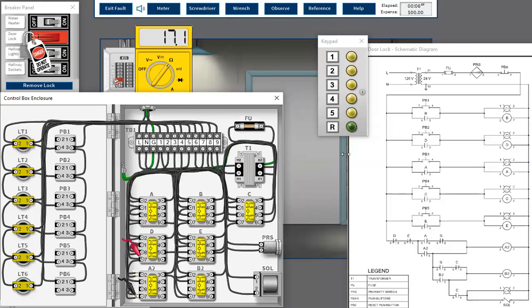All right, so also I would check neutrals back to your neutral wire. So if I terminate and I check 7, I should get 0 from there back to neutral. If you look here, that's your neutral or X2, whatever. You go back to ground, actually. You should be reading 0 all the way through here. So I notice I got my leads flip-flopped. All right, so I should be reading 0 from each one. All right, so everything looks good there.